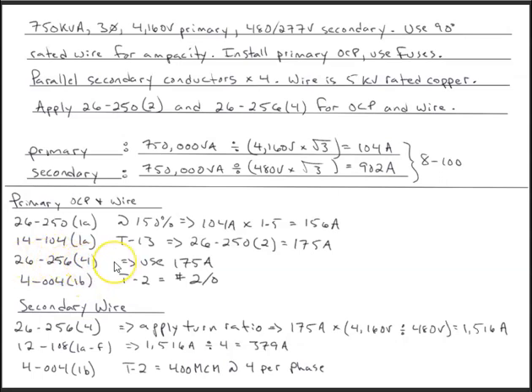26256 subrule 4 here. We're going to use 26256 subrule 4. We're going to use 175 amps here, and then in this portion we're going to apply the turn ratio to calculate for our secondary current. Because we're over 125% here, in first level we dealt with 125% on the primary, 125 on the secondary. Here, because we're over 125, we're going to use this value.